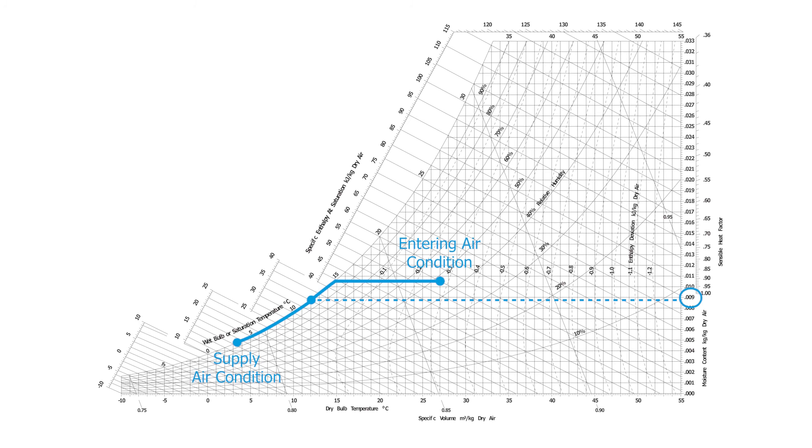If we also plot this on the psychrometric chart, we can see that three and a half degrees dew point has a moisture content of approximately five grams per kilogram of dry air, which is almost half that of the conventional DX system's supply air. With this significantly lower supply air moisture content, the humidity of an indoor space can be maintained at much lower levels.